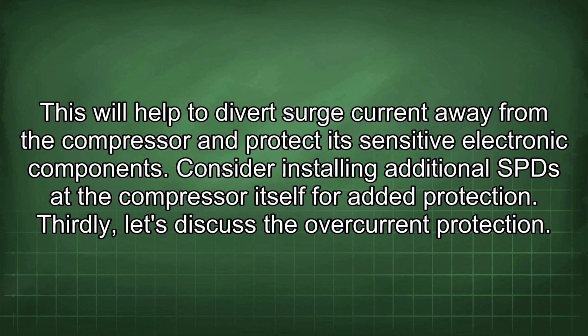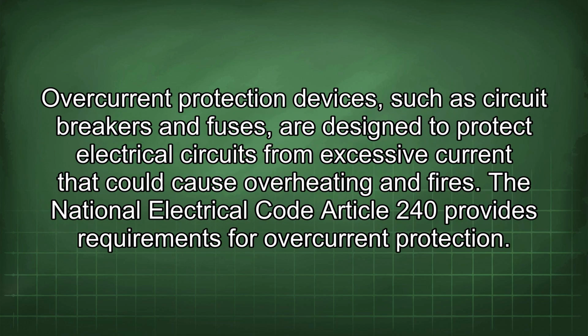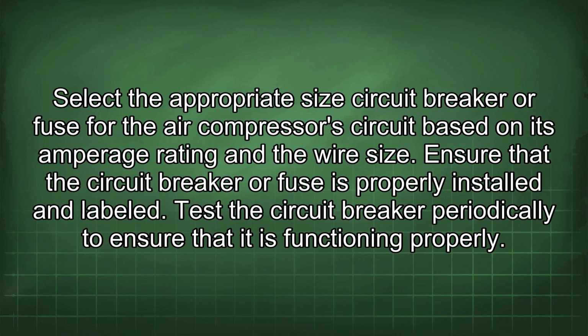Thirdly, let's discuss the overcurrent protection. Overcurrent protection devices, such as circuit breakers and fuses, are designed to protect electrical circuits from excessive current that could cause overheating and fires. The National Electrical Code Article 240 provides requirements for overcurrent protection. Select the appropriate size circuit breaker or fuse for the air compressor's circuit based on its amperage rating and the wire size. Ensure that the circuit breaker or fuse is properly installed and labeled. Test the circuit breaker periodically to ensure that it is functioning properly.